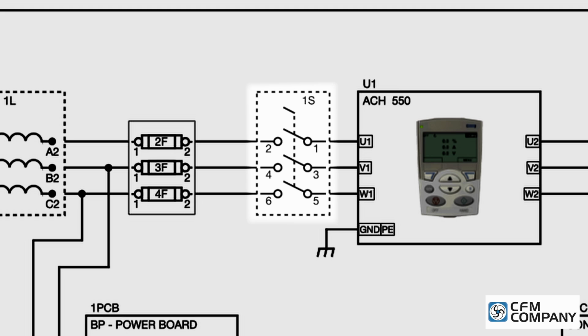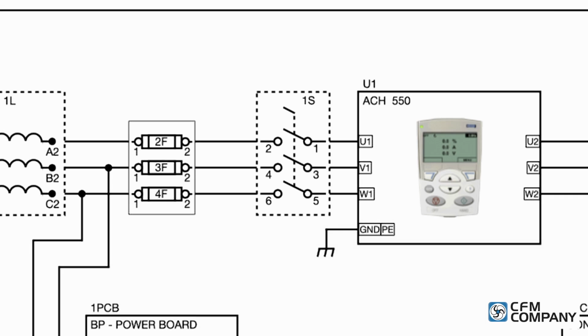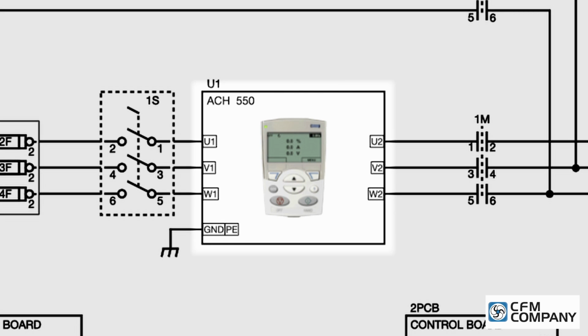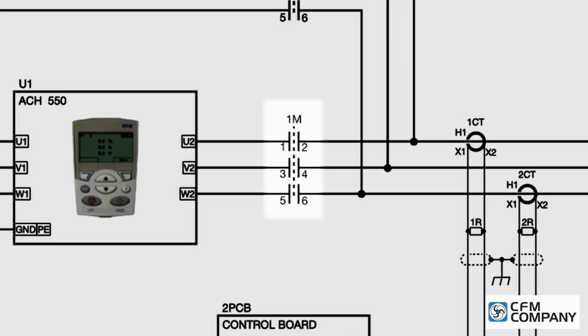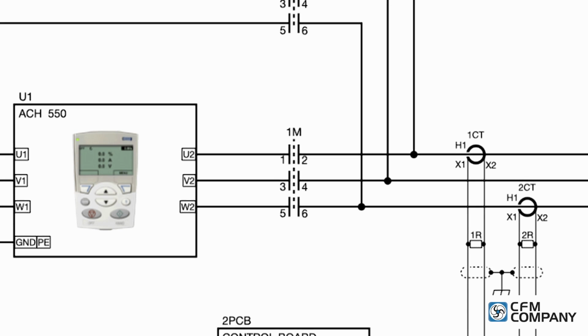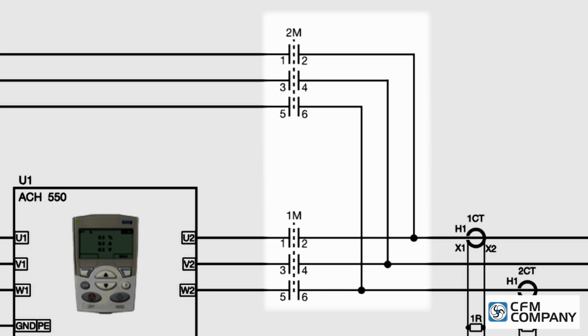If equipped, the drive may have a drive service disconnect. The power is then connected to the drive input terminals U1, V1, and W1. The drive output terminals U2, V2, and W2 are connected to the line side of the drive contactor, 1M. The output of the bypass contactor, 2M, is wired in parallel to the output of the drive contactor, 1M.